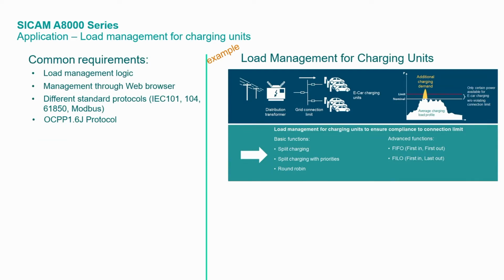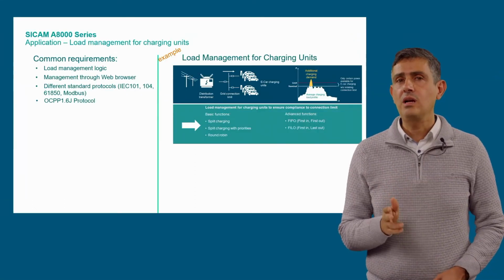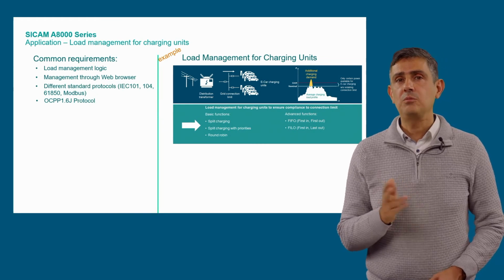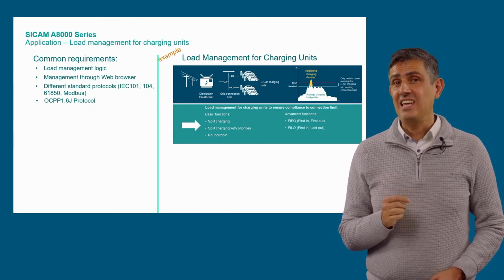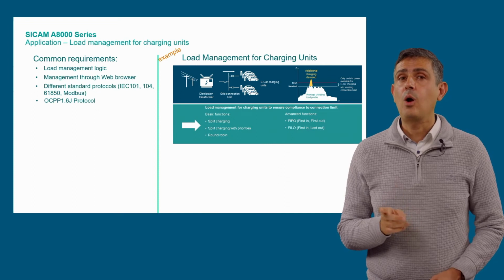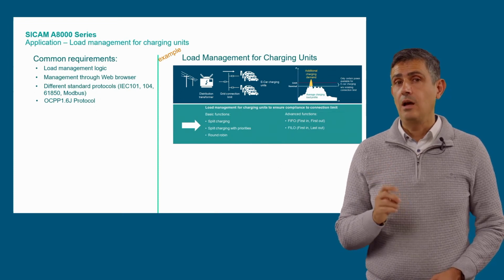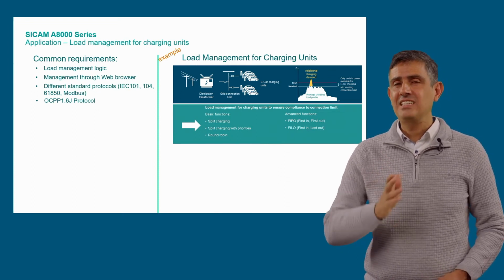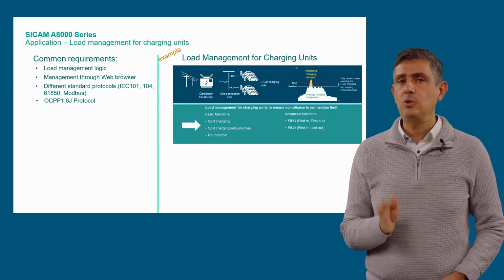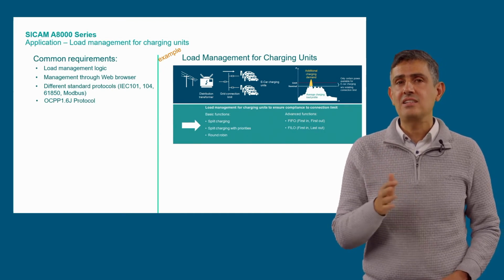The solution for this application must provide a way to interface with the system in order to allow the management of different load management strategies. The load management system must also interact with devices and with external systems through different communication protocols such as IEC101, 104, 61850, and Modbus. Finally, the e-charging system must be able to communicate through the OCPP protocol. The Open Charge Point Protocol has become the default standard for communication between electric vehicle charging stations and a central management system.